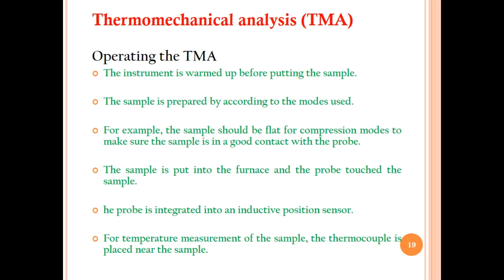The sample is put into the furnace and the probe touches the sample. The probe is integrated into an inductive position sensor. For temperature measurement of the sample, the thermocouple is placed near the sample for accurate measurement of the temperature when force is applied to the sample. The TMA system is operated at a slow rate to get accurate and reliable results. If the specimen expands or contracts, the probe will be moved. By applying force on the sample from the force generated by the probe, the sample temperature changes in the furnace, as already discussed in the former slides in the block diagram.